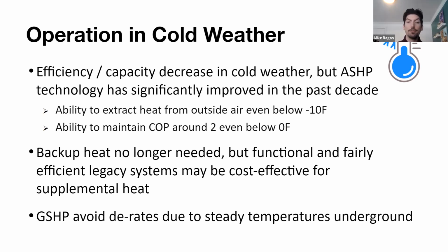But with that said, we do have fully functional and efficient legacy fossil fuel driven systems that are out there. And building owners oftentimes want that to be integrated into their VRF or heat pump systems. That's perfectly fine. We do that every single day. There's no use in ripping out a boiler system that's 10 years old if it's functioning perfectly fine. Great, let's keep it in there and let's stage the equipment so that the boiler doesn't need to kick on until it gets 10 degrees or below outside, because maybe once it's 10 degrees, it's more cost effective to switch over to natural gas or oil. And you could take a look at your own utility bills and find out that exact case. Regardless, if you have that legacy system on site, we're more than able to tie it in with that existing system.